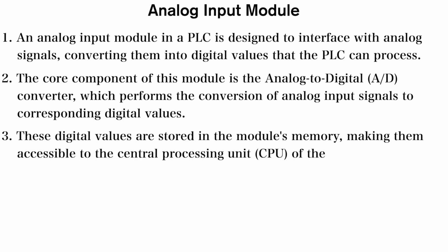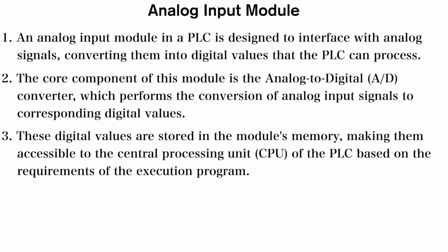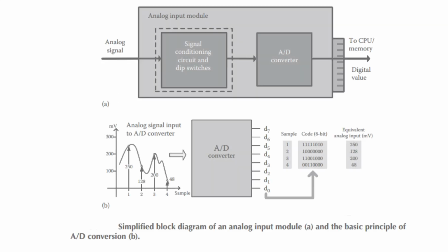These digital values are stored in the module's memory, which makes them accessible to the central processing unit, or CPU, of the programmable logic controller based on the requirements of the execution program or the operation. To manage the variety of analog signals from the different sensors or transducers, the analog input module includes a signal adapting block. Now, what is a signal adapting block?